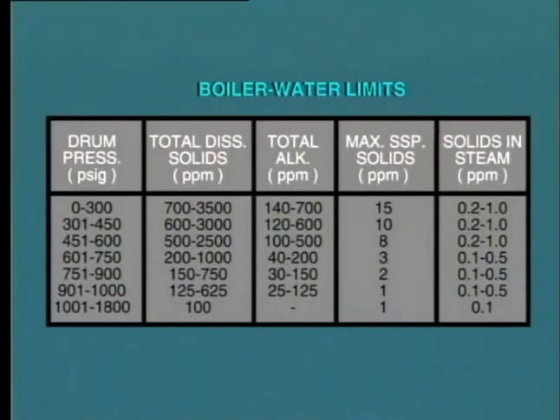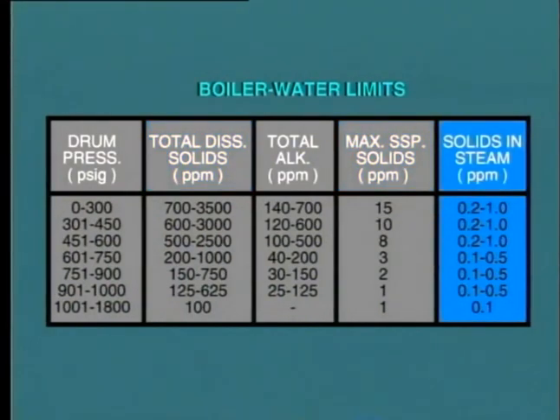Where boiler water contains a high concentration of solids, you should expect frequent tube failures, with the resultant need to take the boiler out of service for repairs. In order to prevent this problem as far as possible, limits are established on the allowable concentration of solids in the boiler water. This table indicates limits for both dissolved solids and suspended solids. The problem of scaling is aggravated at higher steam pressure because of the higher saturation temperature of the water. Therefore, as we see here, the permitted limit of concentration is much lower when the boiler operates at higher steam pressure.